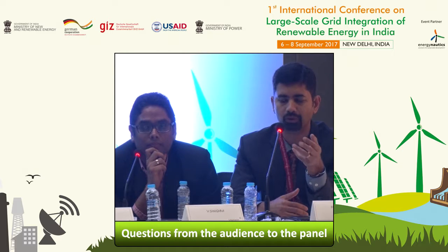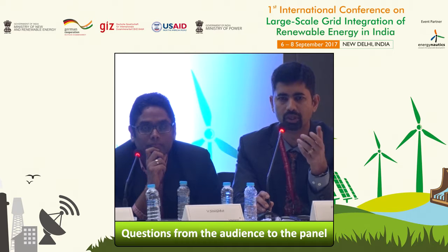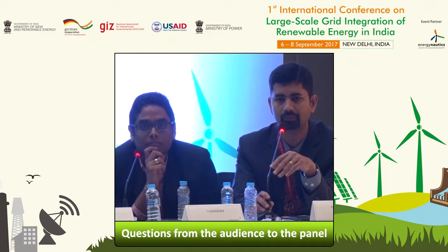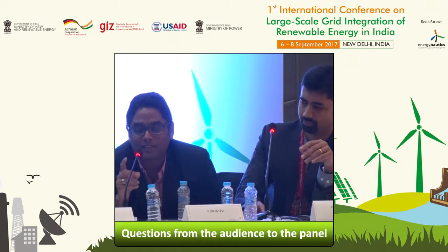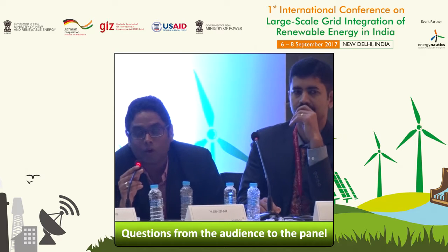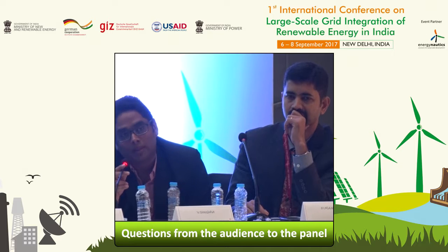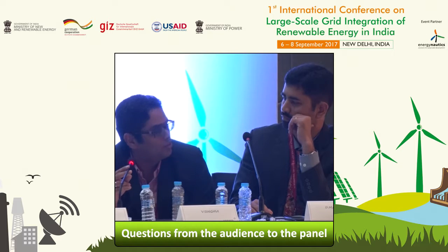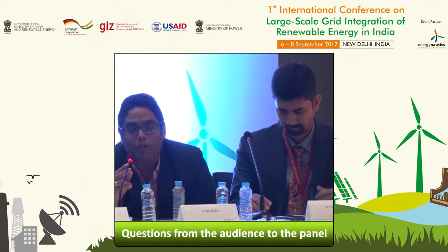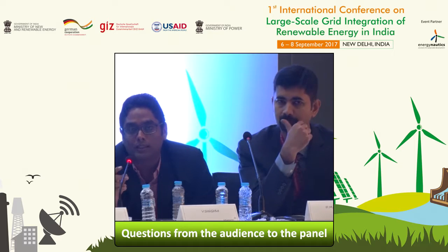So even though we perform these studies, we've not found any issues or constraints to date primarily driven by small signal stability. And it's not really because of the wind penetration; it's when you start displacing a lot of central station generation that you start seeing this problem. I think there is a requirement that for any major change in the generation fleet, they have to do a small signal stability study.